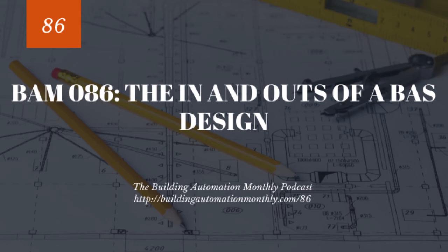And those components are, here's what I see them as, right? You're going to have the title page and legend, which are always there. You always are going to have a title page and legend. And then you're going to have network risers, system drawings, controller drawings, electrical details, and a bill of materials. So those are the 7 things that are almost going to be constant. I can't think of really a project where I didn't provide all those things. I really can't think of one.